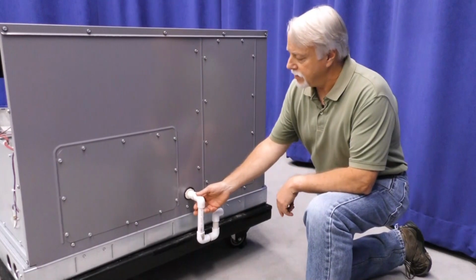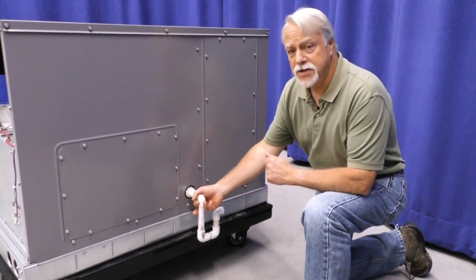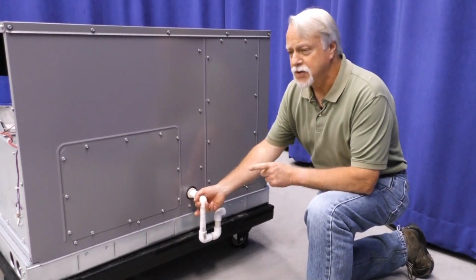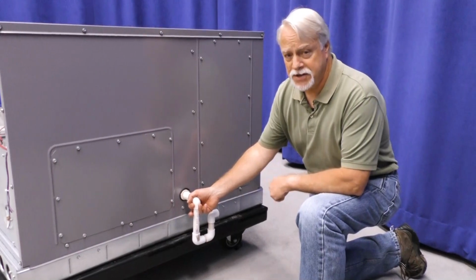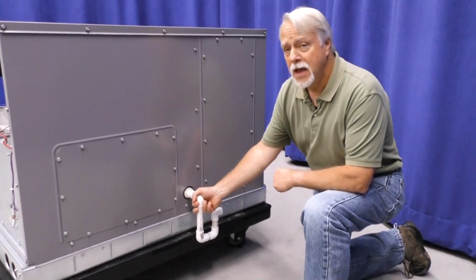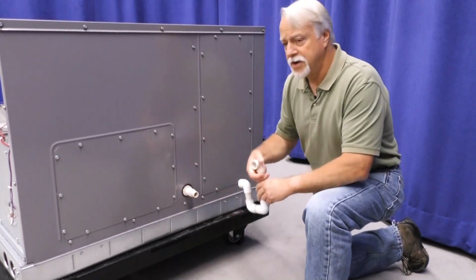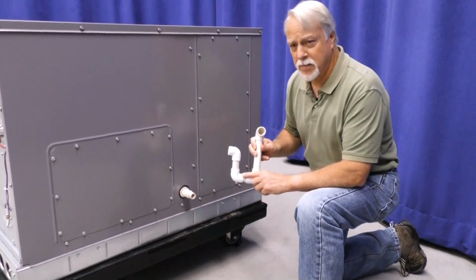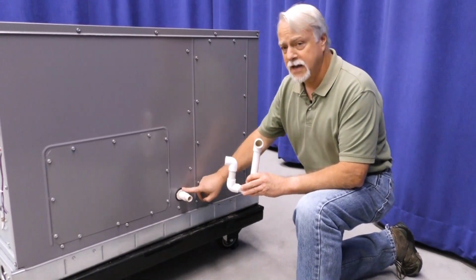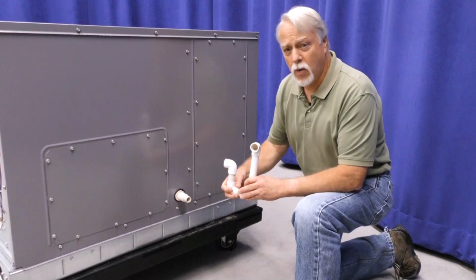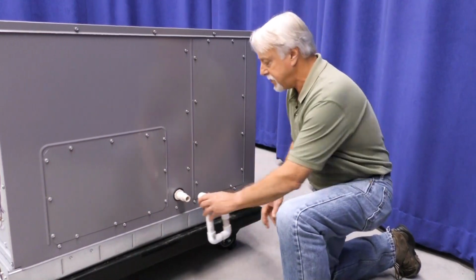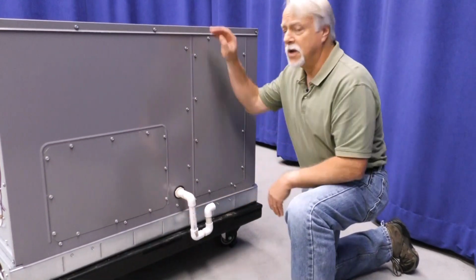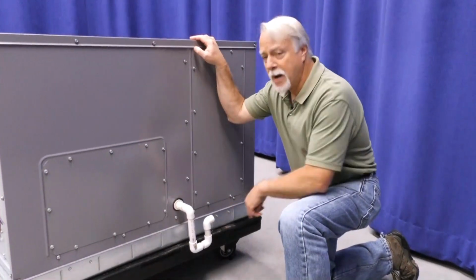It's important to note that every unit requires an external trap, and that trap be built using the dimensions in the installation instructions. Additionally, it is important to note that the trap is a service component. Ultimately, just like the condensate pan, this will require some level of cleaning or maintenance. Consult the installation instructions for the proper dimensions.